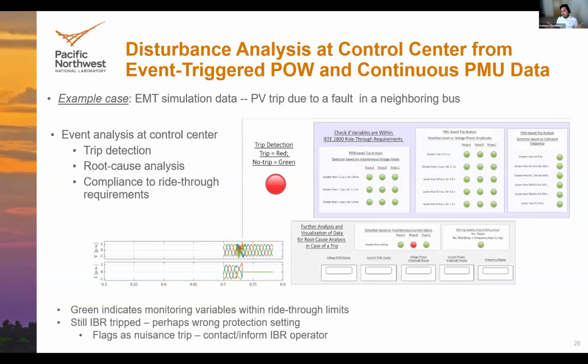So we built a platform in MATLAB just to analyze this and to see what ride-through compliance is happening here. As you can see, we have one specified functionality to check whether it's a trip or a no trip, which gets red, meaning it's showing us there's a trip, which is very easy to pick from the current measurements alone. But what is more complicated and involved is to see what led to the trip, or if the trip was within the ride-through performance mandates. So we have the requirements here as per the IEEE 2800 ride-through requirements, which say whether the voltage was within or outside these magnitudes for this time duration, and the same with the frequency. And everything here being green indicates that the performance variables, or the monitoring variables, were within the ride-through requirements, but we still see a trip.